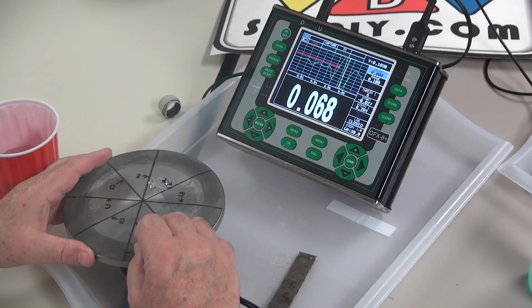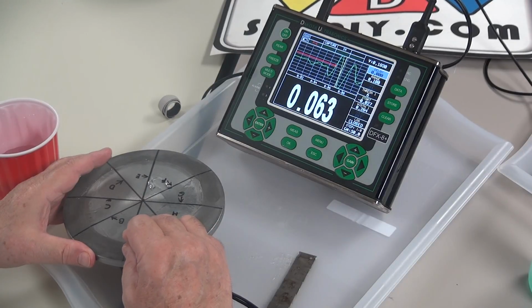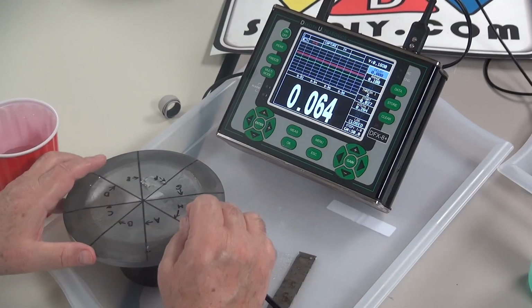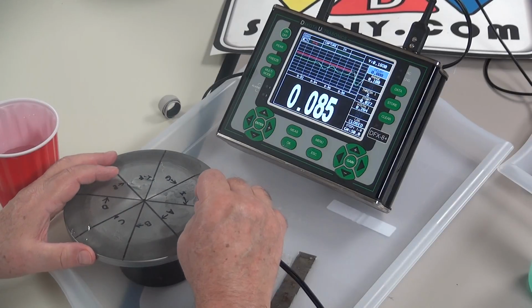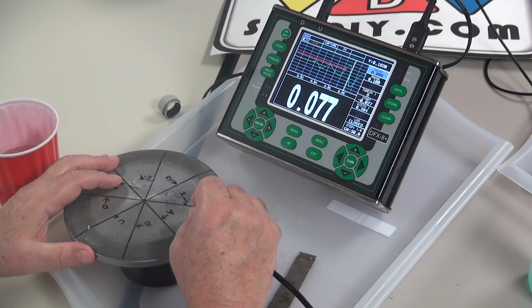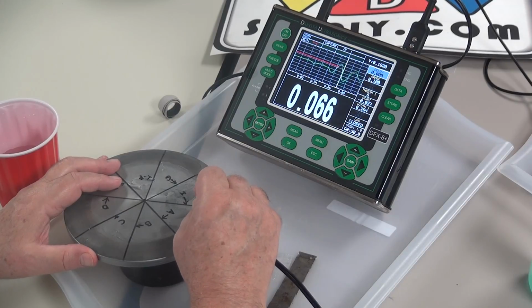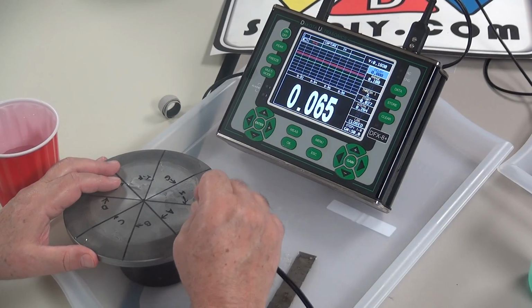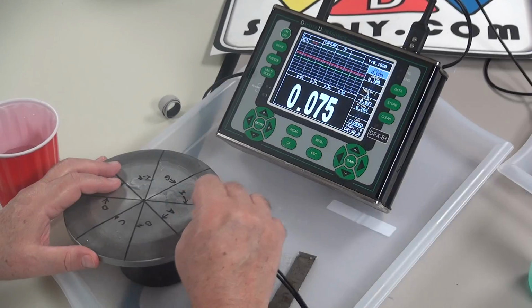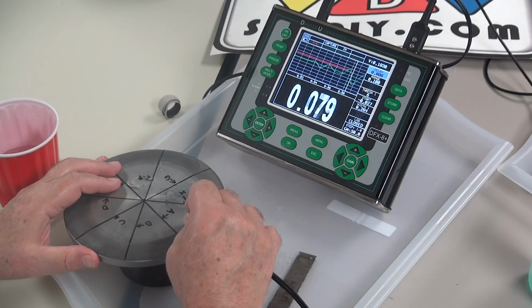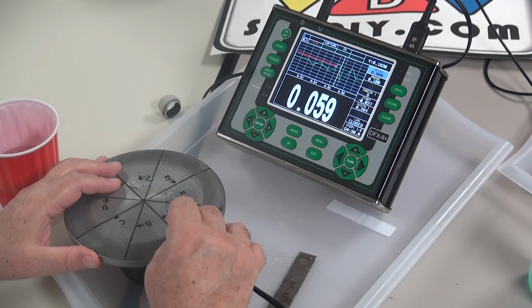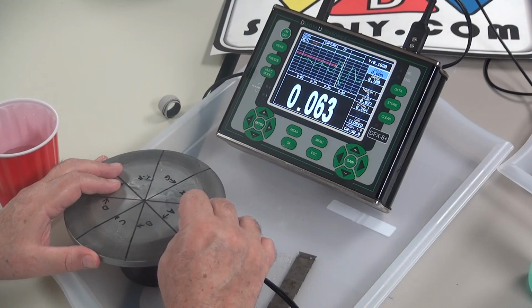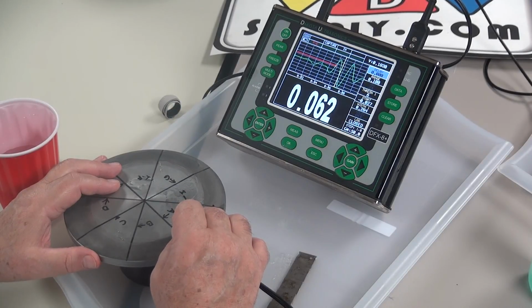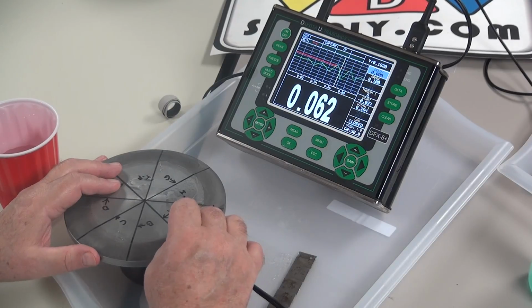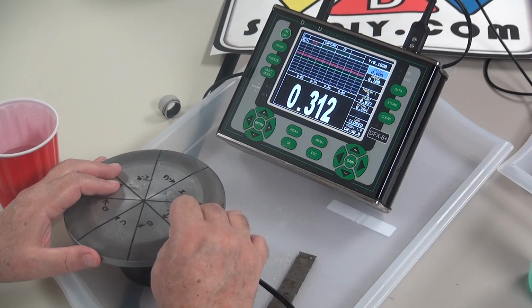Scanning slow enough, keeping constant pressure takes a little bit of getting used to. Once an operator gets used to it, I think they'll do a lot better than I am doing. Just getting the probe to just skate along the surface without raising it up. If you raise up the probe, you build up couplant underneath it and the readings are going to increase. So the probe has to be kept firmly down against the material.